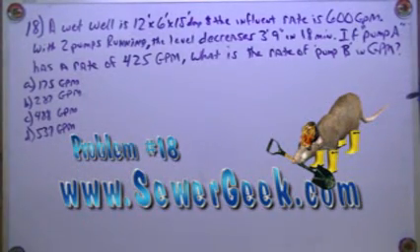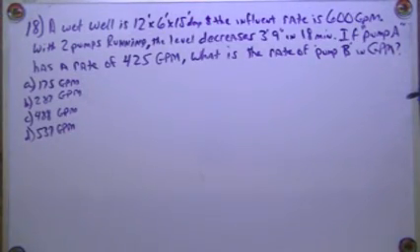Problem number 18, wastewater collection math book sewergeek.com. A wet well is 12 feet by 6 feet by 15 feet deep, and the influent rate is 600 GPM. With two pumps running, the level decreases 3 feet 9 inches in 18 minutes. If pump A has a rate of 425 gallons per minute, what is the rate of pump B in GPM?